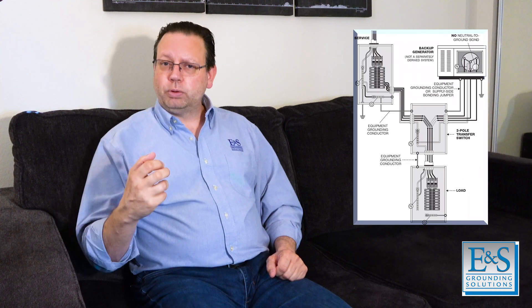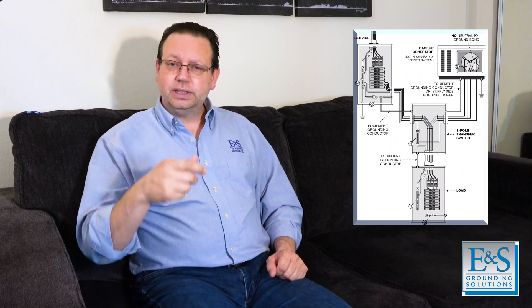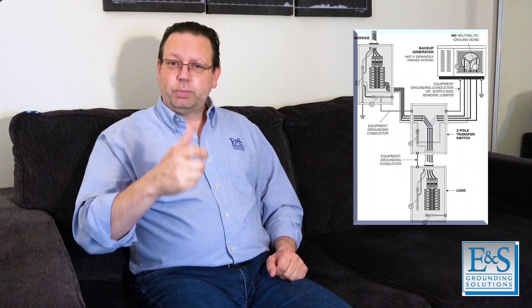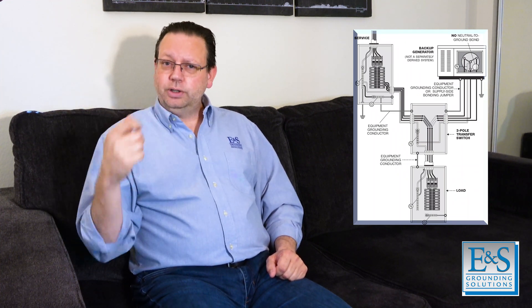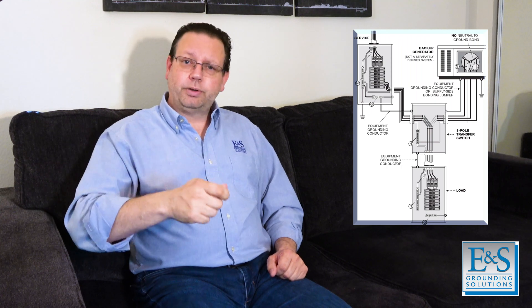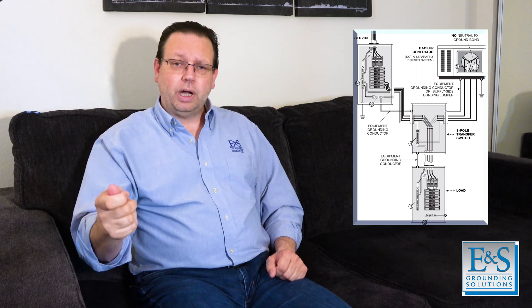Another place this happens is when you put in an automatic transfer switch. You have three-pole and four-pole transfer switches. In the case of a four-pole switch, you need a neutral-ground bond in the generator, but in a three-pole switch you do not. People get that mixed up, and all of a sudden you're allowing neutral currents to travel back on the ground system.